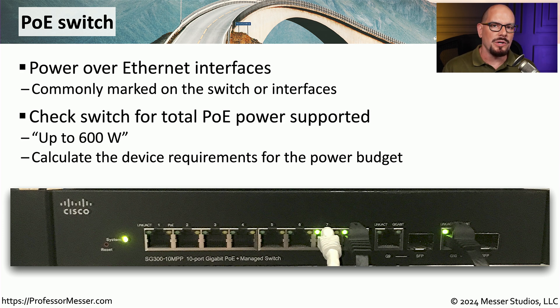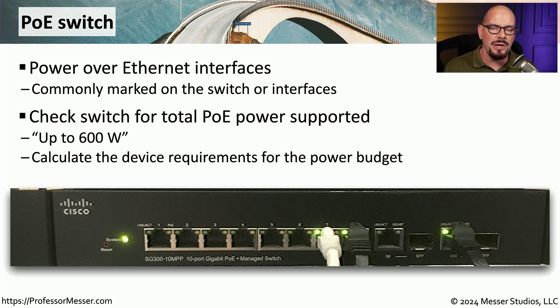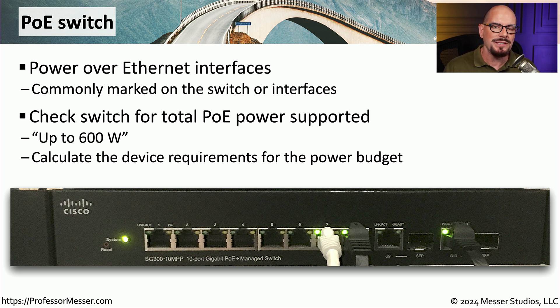You'll also want to check the switch specifications to see the maximum amount of POE power that switch can support. For example, the switch may support 200 watts of POE, or it may support 720 watts of POE. You will need to add up all of the devices connected to that switch, determine their maximum power draw, and make sure that total is under the capacity of that particular Ethernet switch.